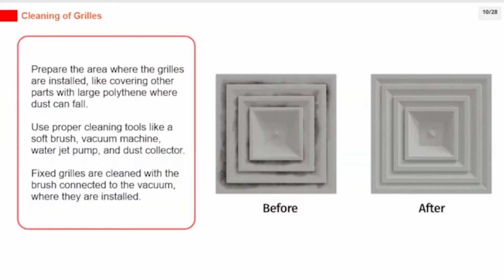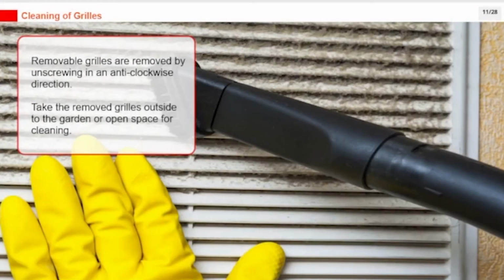Prepare the area where the grills are installed, like covering other parts with large polythene where dust can fall. Use proper cleaning tools like a soft brush, vacuum machine, water jet pump, and dust collector. Fixed grills are cleaned with a brush connected to the vacuum, where they are installed. Removable grills are removed by unscrewing in an anti-clockwise direction. Take the removed grills outside to the garden or open space for cleaning.